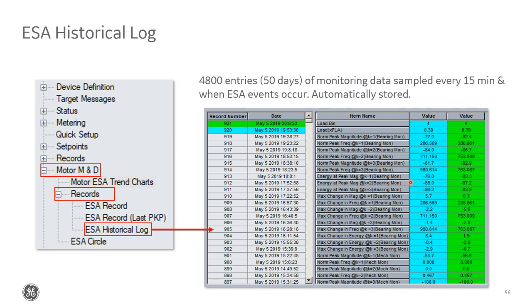The historical log, again, is basically just a large data logger. Every 15 minutes, we'll take a sample of what the readings are, and we will store all of those peak magnitude values, the energy values, all the change values, what load bin we're operating in, all the motor's running characteristics, basically all the operational info in the historical log. That's stored every 15 minutes, and that's for if you want to go back and actually look at the values. This is the only place where you can see past values. If you look in any of the metering screens, you'll see what the current sampled values are.